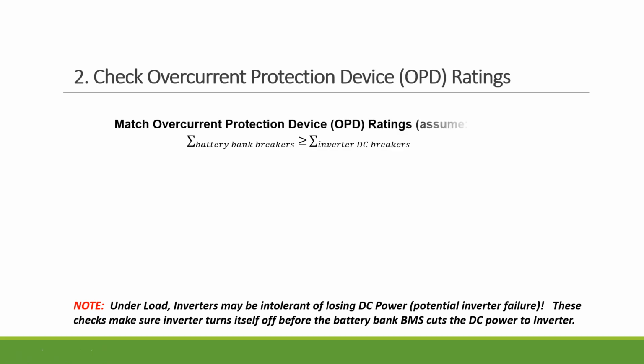And second, you want to go check the overcurrent protection device. Basically, on the inverter there's a breaker, and there's also a breaker on the battery. Now you want to make sure the inverter's breaker size is smaller than the battery bank's breaker size. And why is that? Because some inverters are intolerant if you lose the DC power.